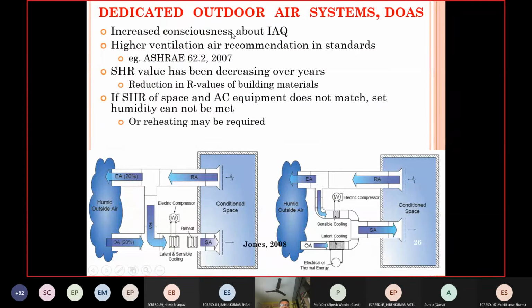So I mentioned the word dedicated outdoor air systems. So what exactly is that? How is it different from the conventional system which takes outdoor air? Now, outdoor air always has to be taken from the atmosphere. Now, in this scenario of the COVID-19 pandemic, we very well understand the need for ventilation, the need for taking outside air and diluting the conditioned space air with the help of that, right? So that the pollutants generated here are regularly exhausted out.